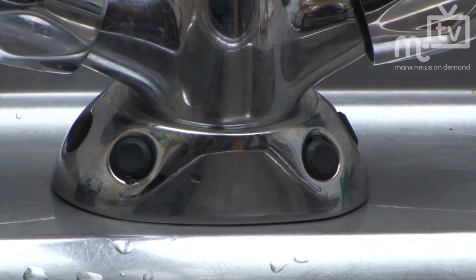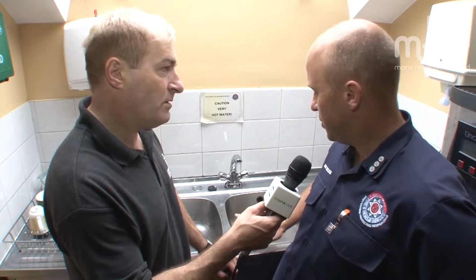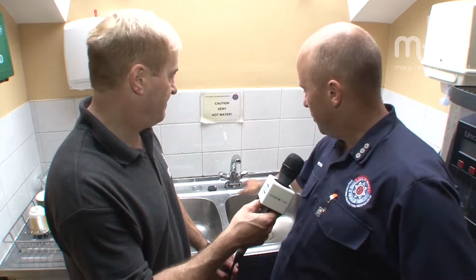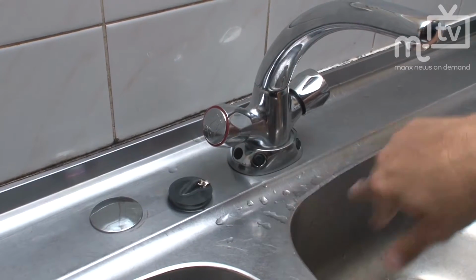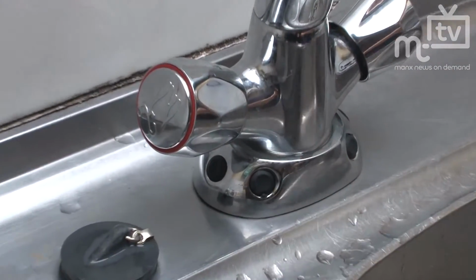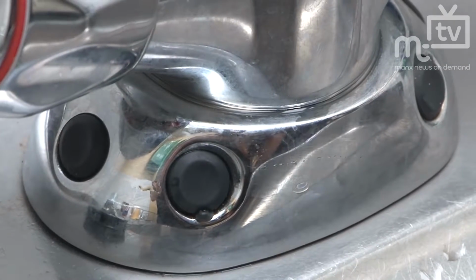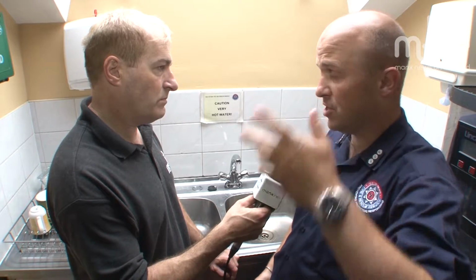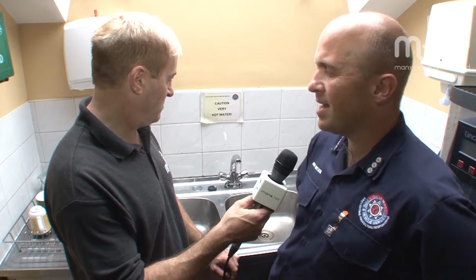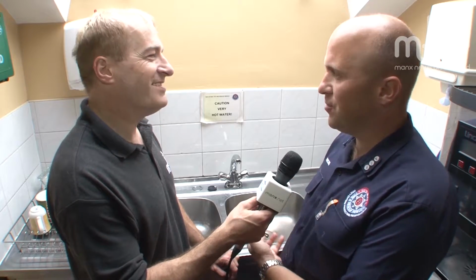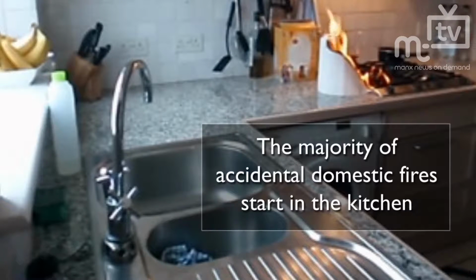Yeah, it's a device called an Automist from a company called Plumis, and it's basically a sprinkler system that fits under the tap. It's retrofitted. The tap was here normally, but the device is actually this part here, and the sink just goes down through it. Underneath the sink, in this case we've gone for the back as a pump. It's connected to a heat detector, which is standard in any new kitchens. If the heat detector gets to 57 degrees centigrade, so again, it's not going to be through burnt toast, it's not going to be through the kettle, it's got to get to 57 degrees centigrade, so anybody that's been on a high temperature holiday will know it's got to get hot.